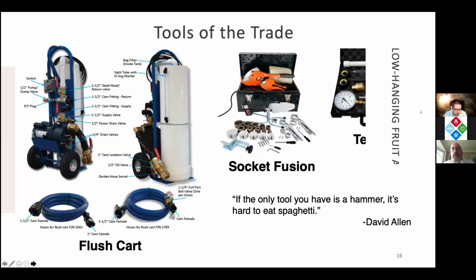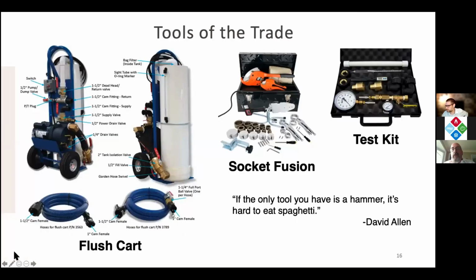One thing we used to do in the past was let that flush cart run so you can work on other parts of the project simultaneously. The longer you let the flush cart run, the more pockets of air and micro bubbles get out of the system, lessening your chance of a nuisance service call just for a bit of air. It does happen, but the longer you let it run before tidying up and leaving, the better.